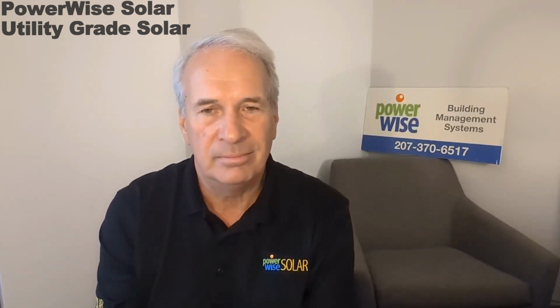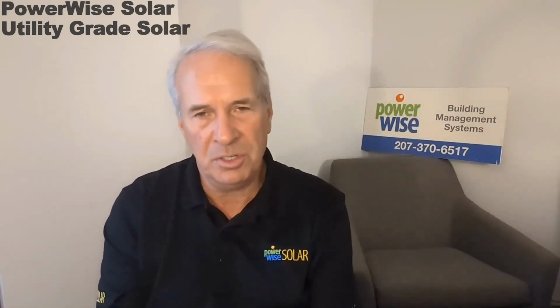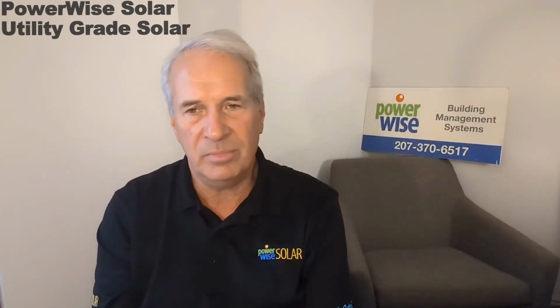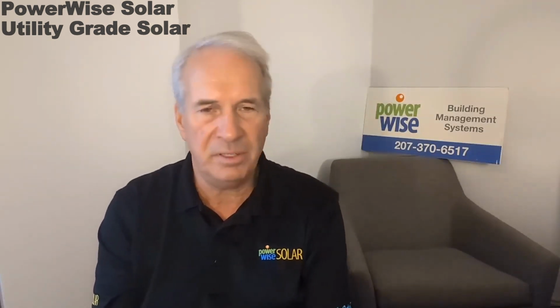And then once you have that data, how is it output into the systems? Could you tell me a little bit about that? Yes, please. The data loggers we use all offer Modbus TCP output via direct Ethernet cable communication, or sometimes via cellular modem. A large majority of utility sites have the data going to a SCADA system. And of course, if you're using a cellular modem, it doesn't have an ongoing data flow, but the modem can update the data in the system at various frequencies that you configure.